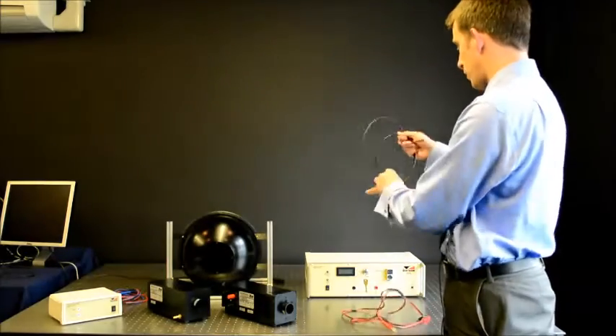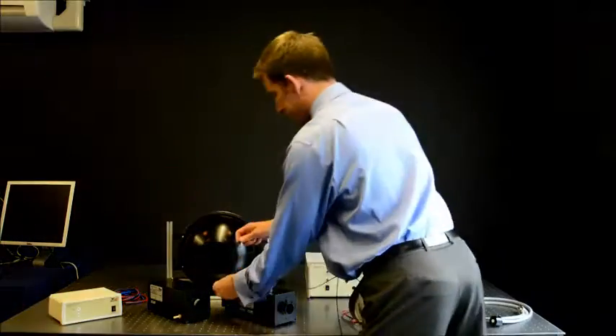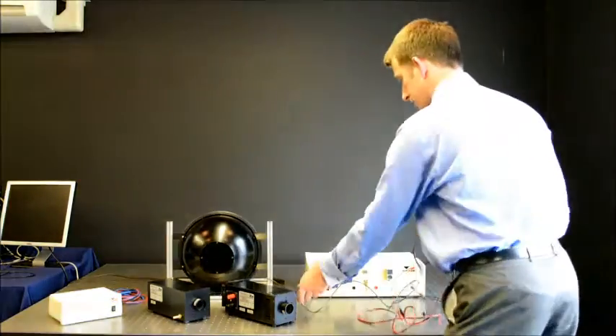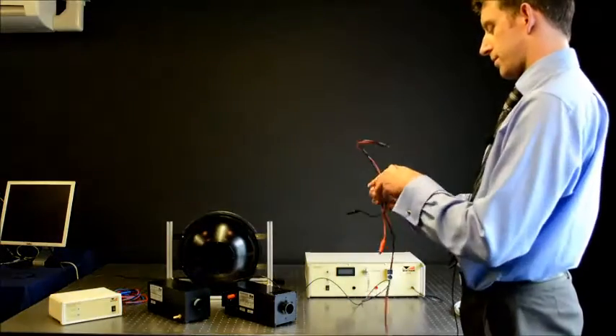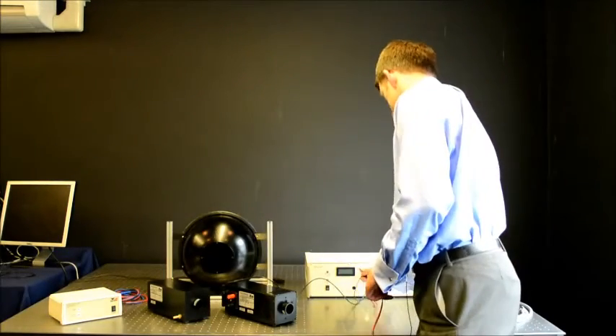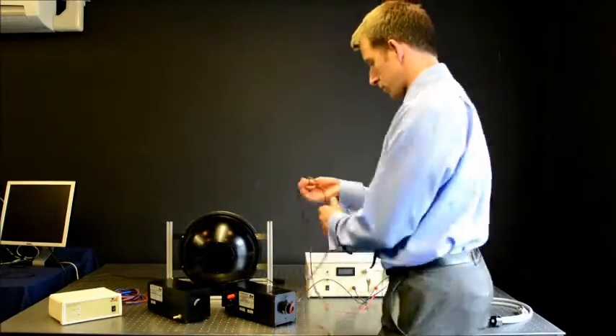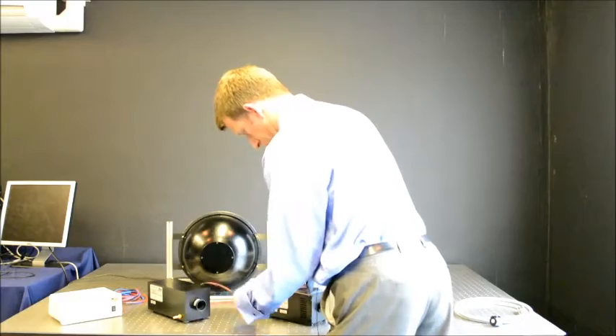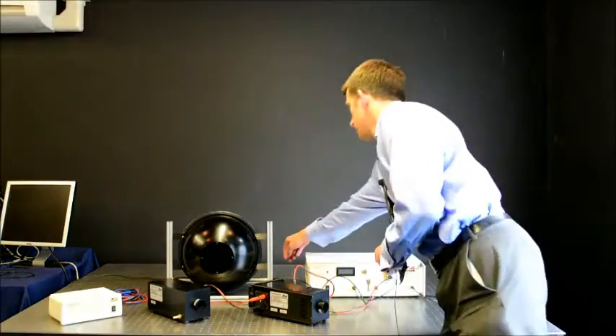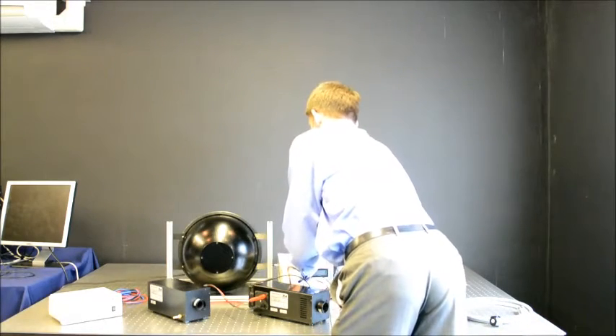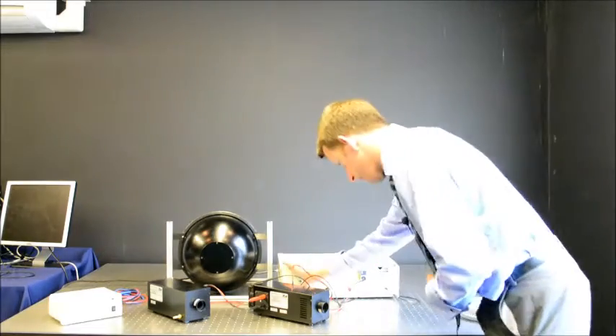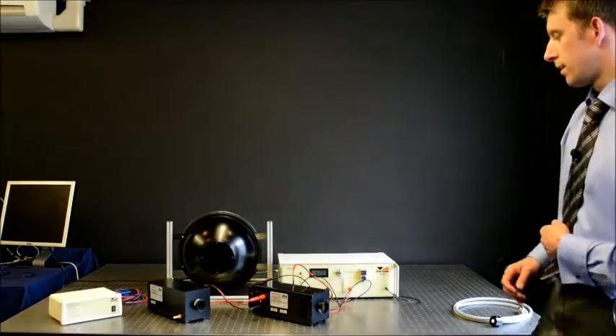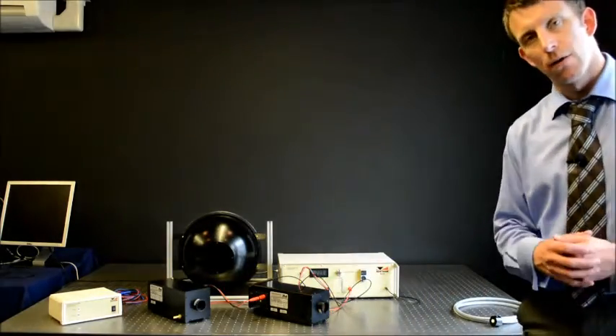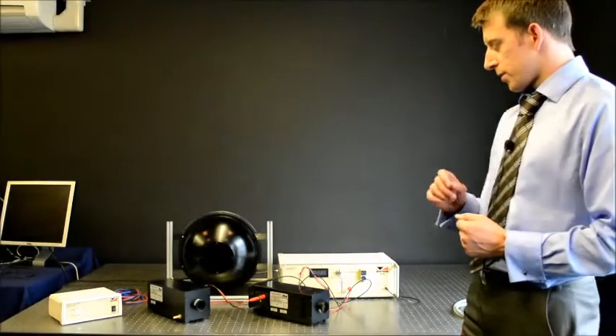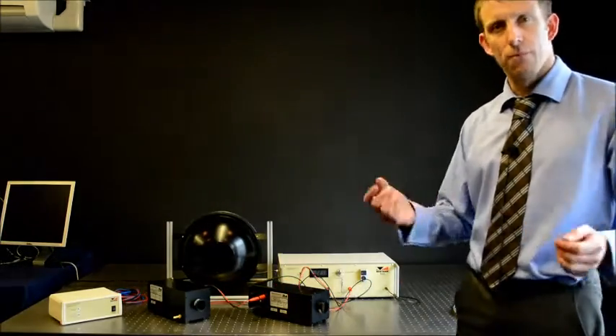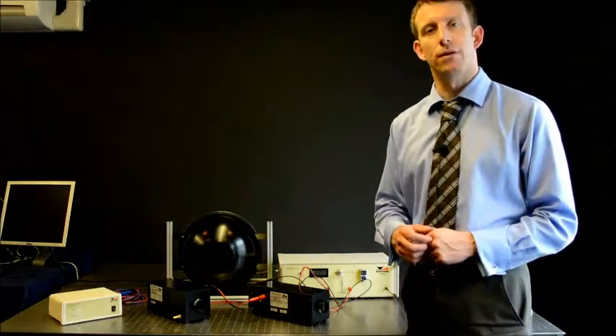The CL6 requires a fan connection from the 605 and the current is provided via red and black cables. Ensuring the current is selected, the mains inlet is connected to the 605. One can power on the source. Warm-up time around 5 minutes is recommended. It's also recommended that you do not move the source when it's on and for some 1 minute afterwards to ensure not damaging the filament.